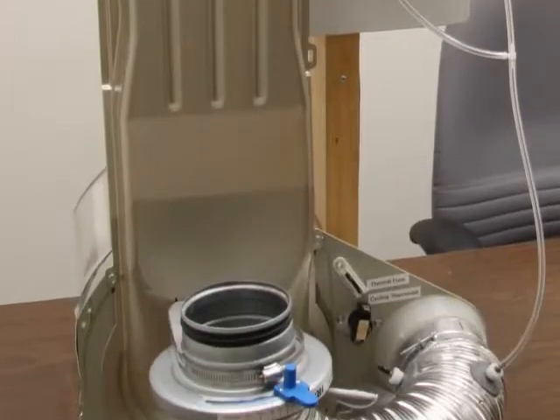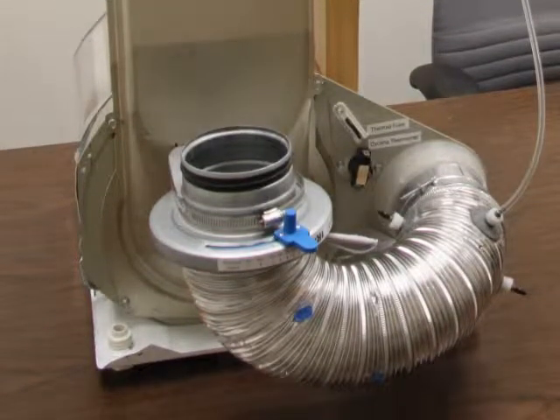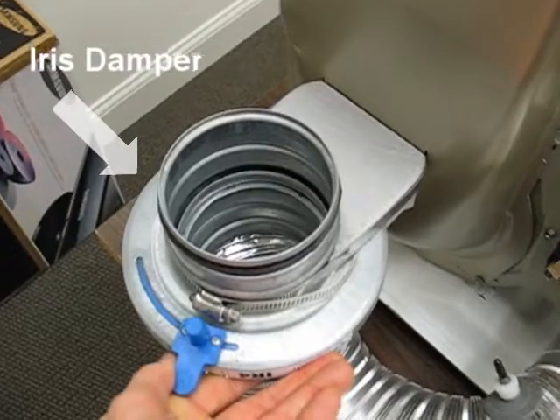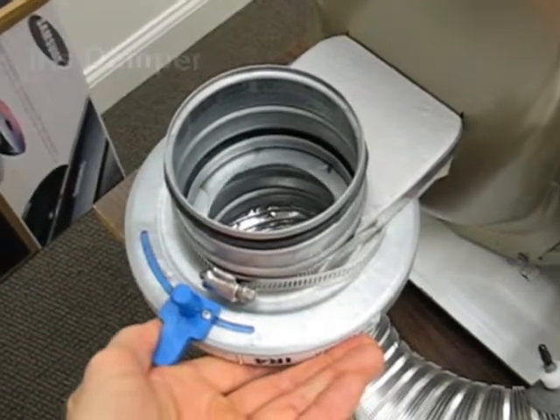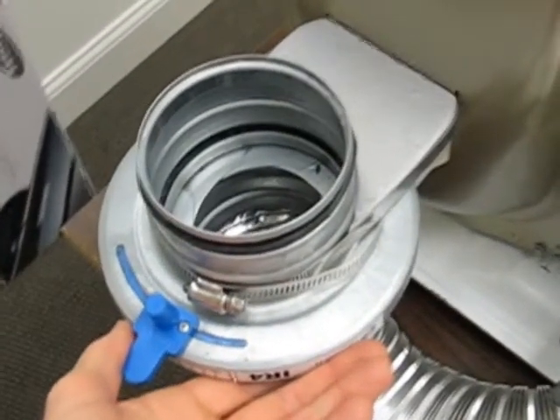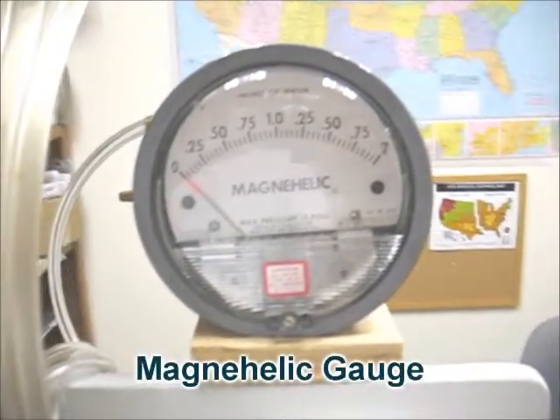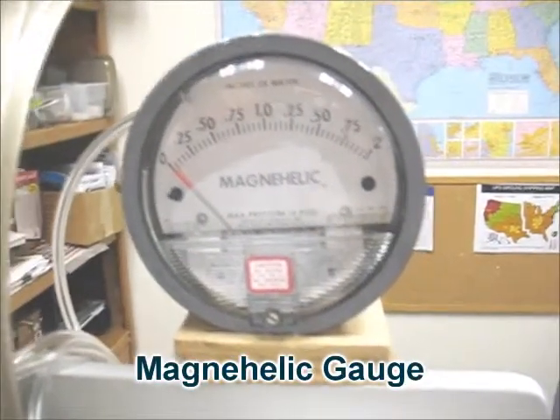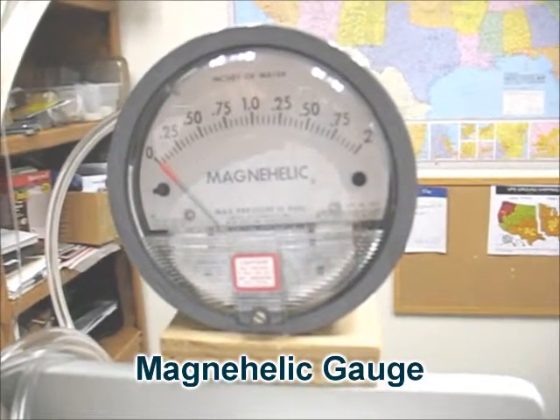Here we've added a typical flex transition hose connected to an iris-style damper that we'll use to simulate lint buildup by closing down the aperture, or choking the airflow. Here we've teed off the tubing to display the analog pressure levels with an industry-standard Magnehelic gauge that quickly indicates low air pressures up to 2 water column inches.